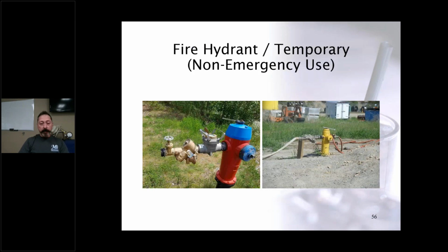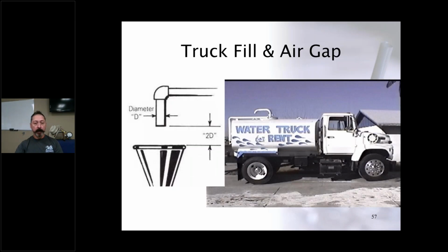A lot of hydrants are being used for other than emergency services. So if anybody's going to connect to a fire hydrant for potable water, dust control, truck connections, or temporary services due to construction sites, there should be a portable RP attached to the side of the hydrant and supported properly for any non-emergency use. For trucks themselves, a lot of the new trucks now will have an air gap at the top of the truck, and if not, then they'll have to ensure that there's an RP on the fire hydrant. One of those two would suffice, but mostly, as far as water purveyors go, they will have a couple of portable backflow preventers that they will install on the hydrant should they allow people to connect to their hydrants for non-emergency water use.